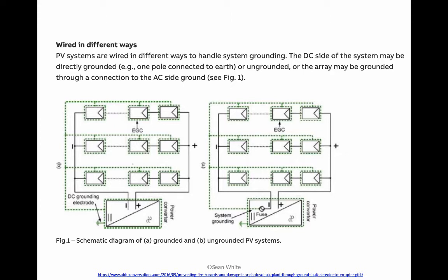So it used to be that this type of inverter on the right, this is showing a negatively grounded inverter, because it's negatively grounded through the fuse. The fuse is connecting the grounding system to the negative. It used to be that we had to make this wire white here in the 2014 NEC and earlier. Then after the 2014 NEC, so in the 2017 NEC, 2020 NEC, this wire cannot be white anymore. And it used to be that we would never open up the circuit. We would treat this like a regular grounded conductor, and you don't open it up when you turn it off. That means you don't turn off the negative, you just turn off the positive to turn it off. Then once the 2017 and later versions of the NEC rolled along, then we were supposed to open up both of these.